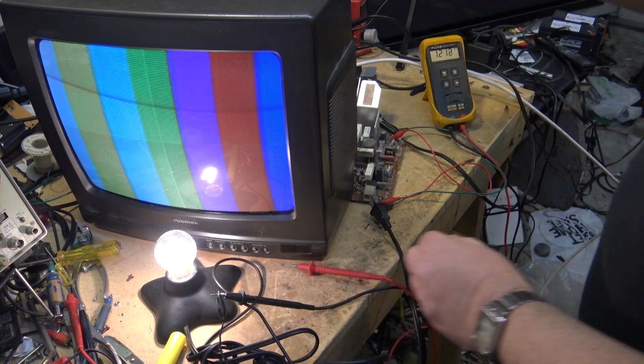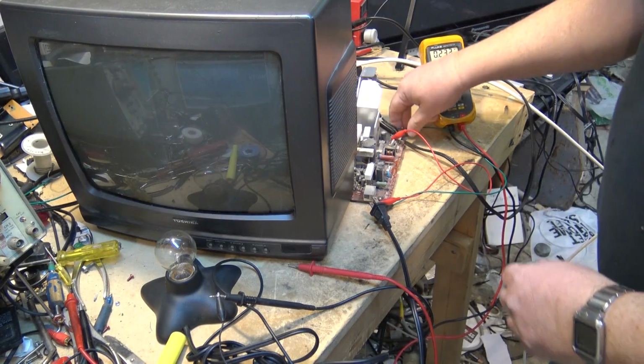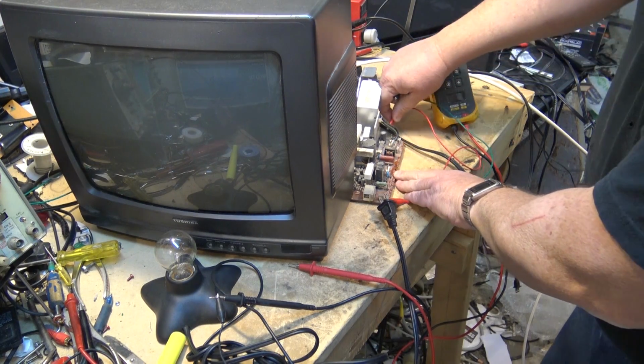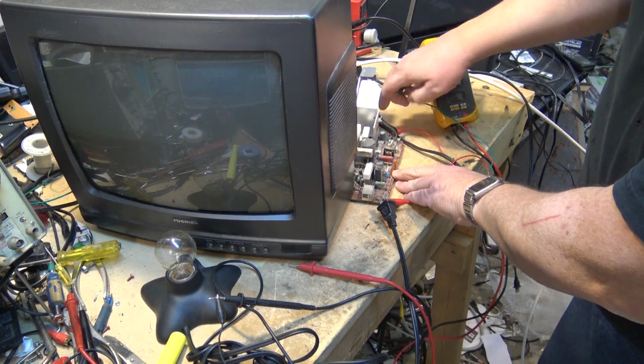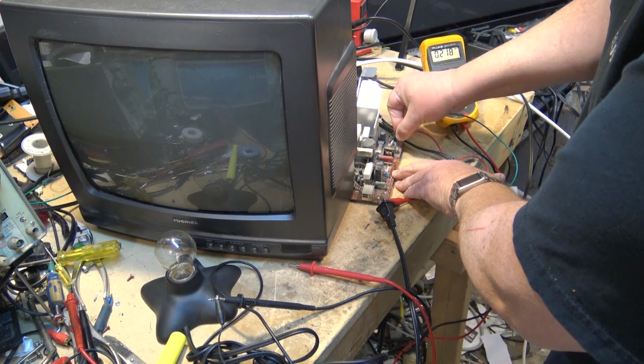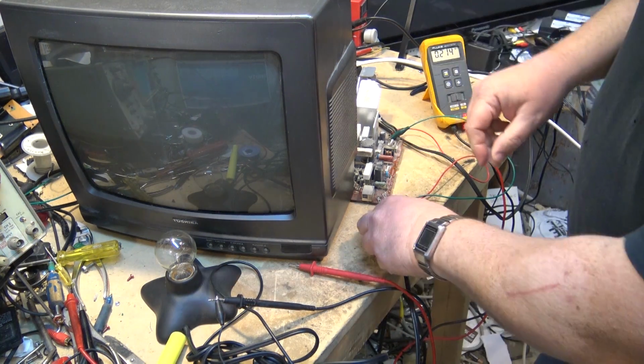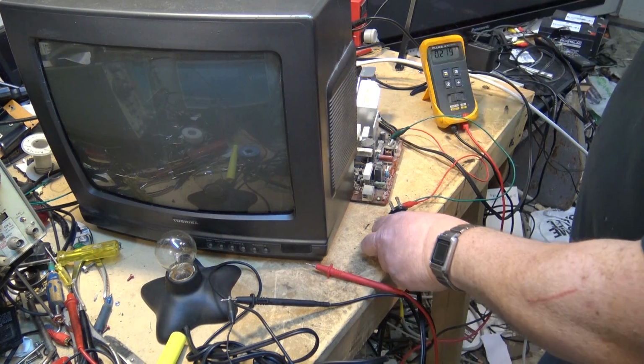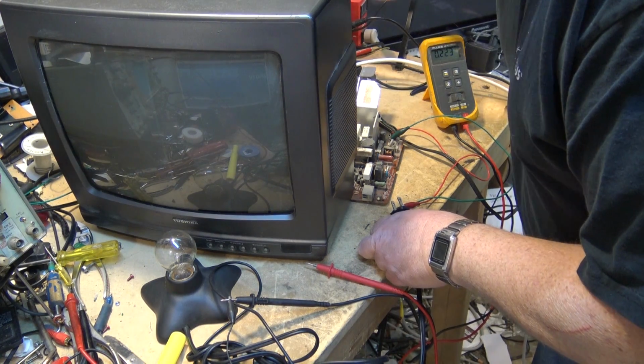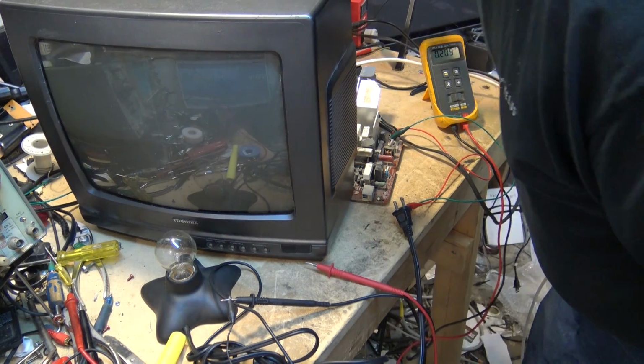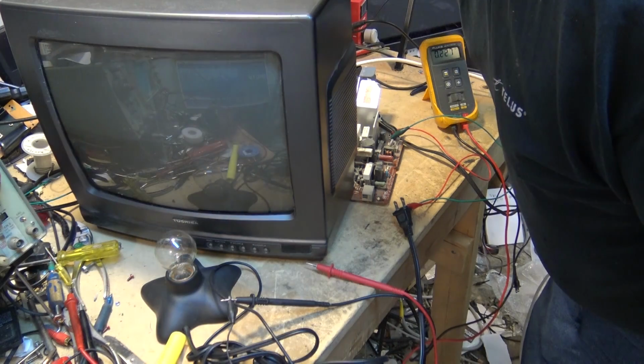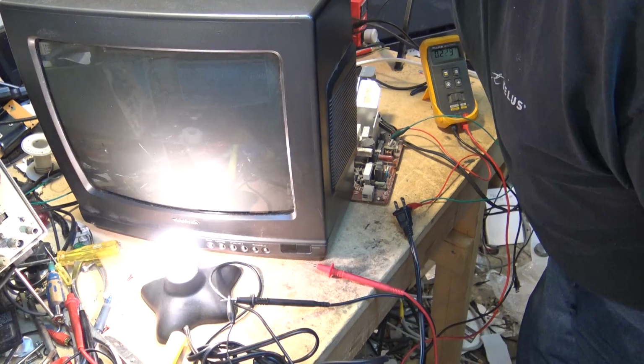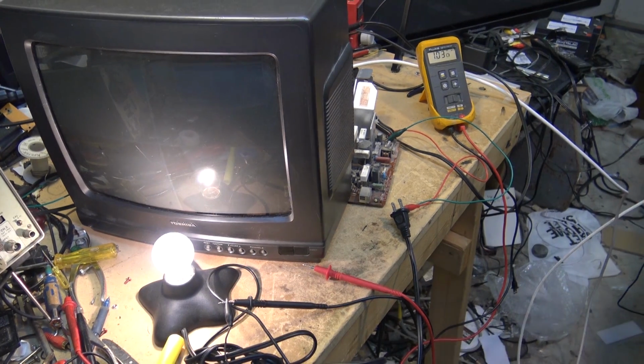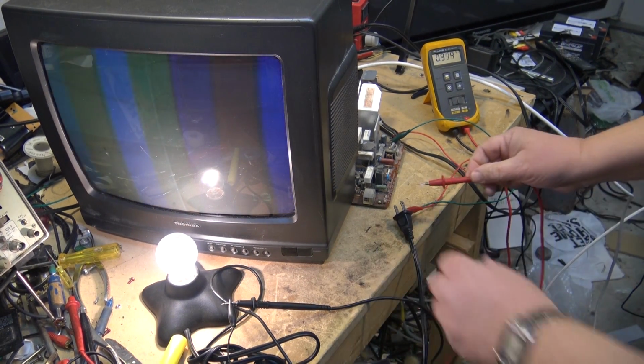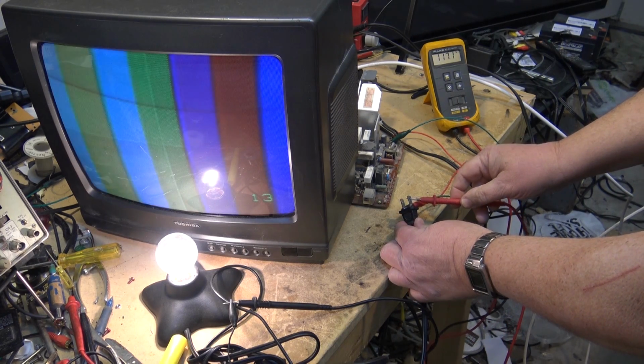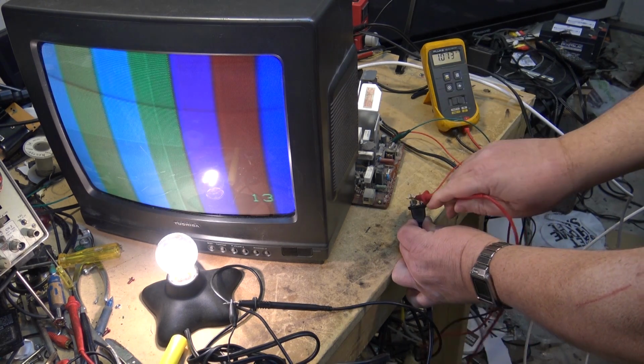What I'm going to do is I'm going to change these two around so that the red is the hot side. Now that we know the red wire here is the hot wire, if I plug into my 120 volts, if I measure to the red, I have 117 volts here, and if I measure to the green, I have zero.